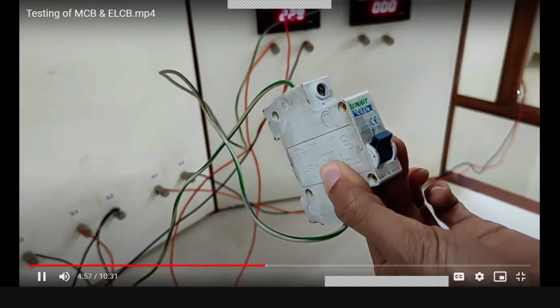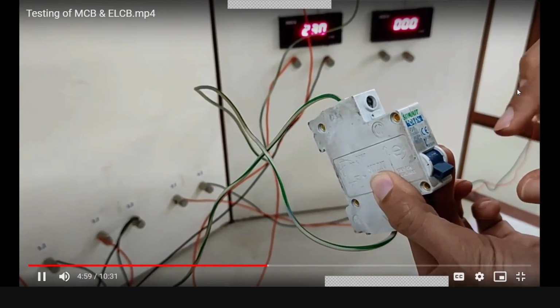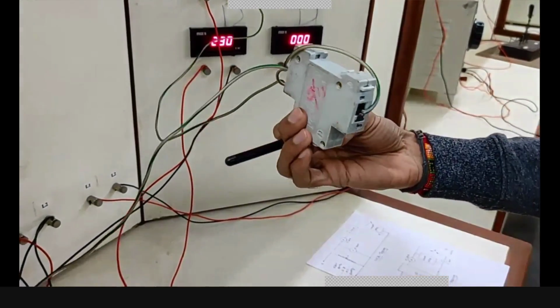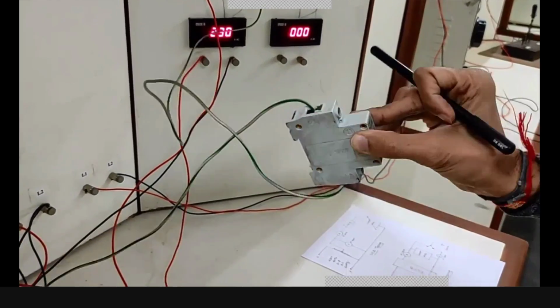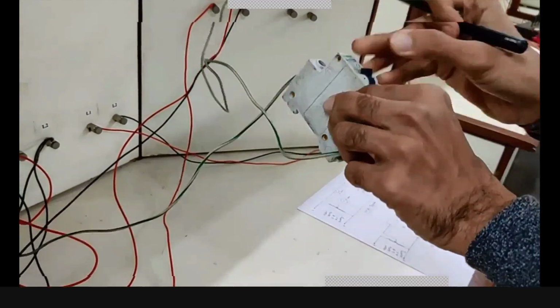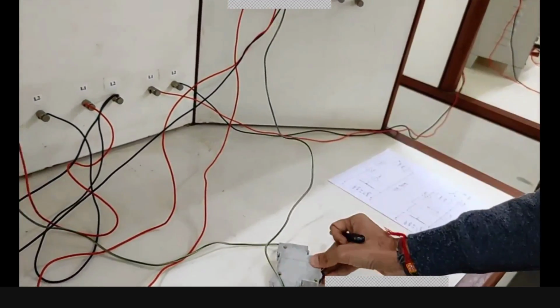This is the on condition, this is the off condition. At present, I will make it on. It is totally enclosed, so we cannot see what is actually inside it, but I can show you - at present it is a totally enclosed MCB. Now we have to check what should be the tripping time of this MCB. This MCB is of 2 ampere rating. Now I will increase the load gradually.